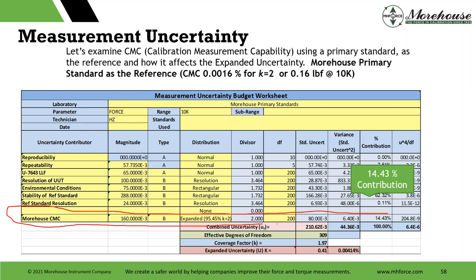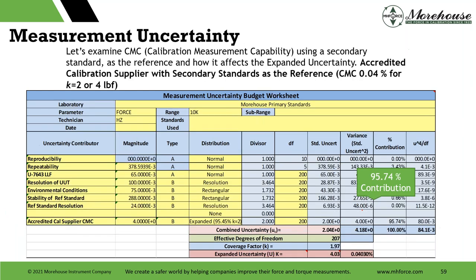If your reference standards are not being calibrated by deadweight primary standards with low uncertainties, this is what we're comparing. So if we work up a full budget, our expanded uncertainty is 0.41 pounds. We have that calibration with dead weight. The calibration with dead weight is quite low versus if we go to a secondary standard supplier based on the traceability chain.